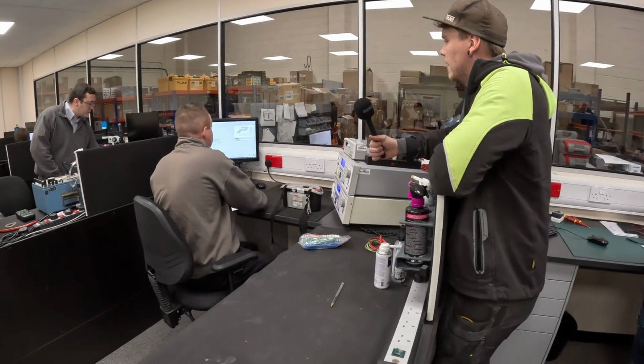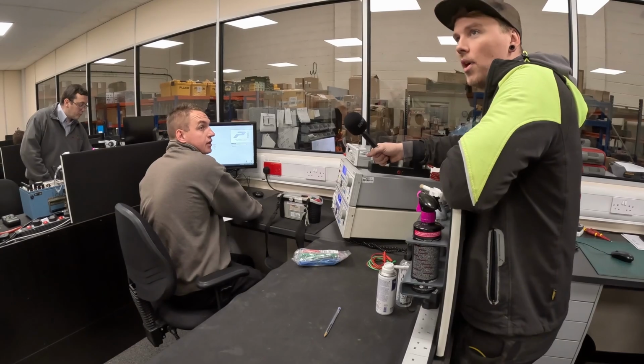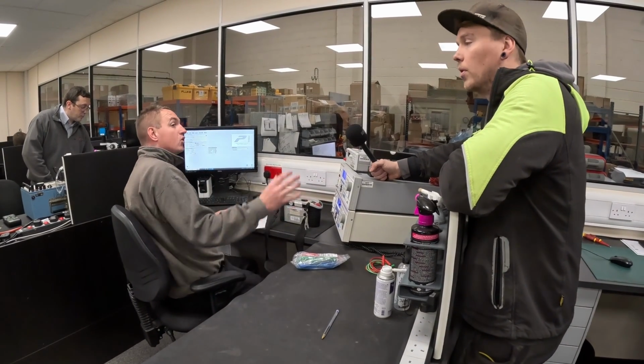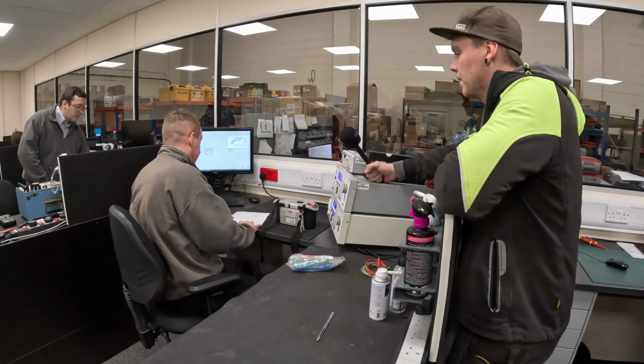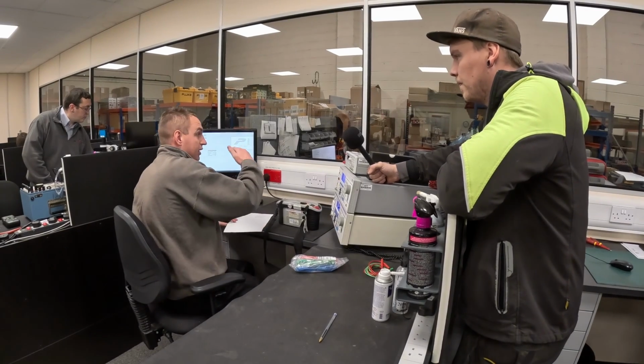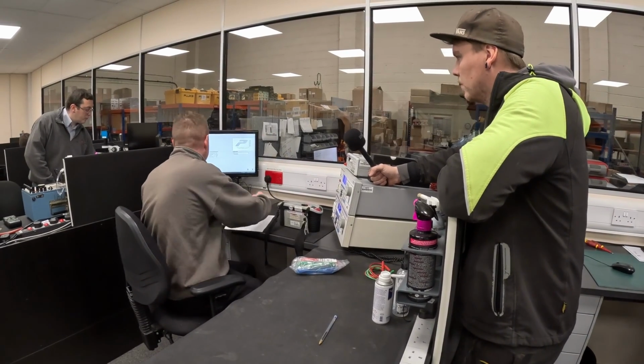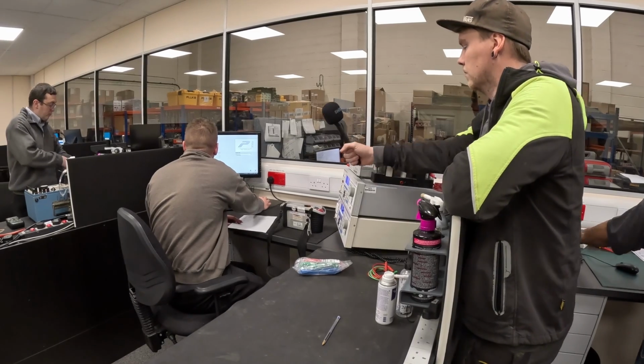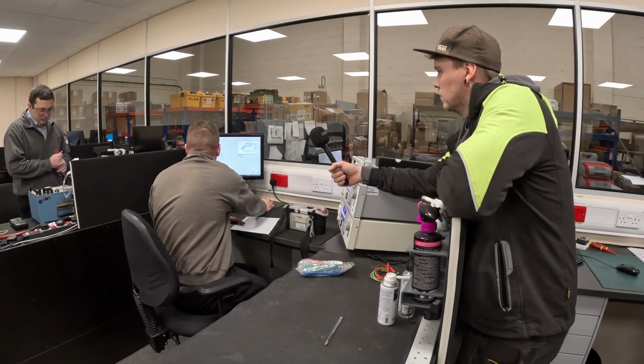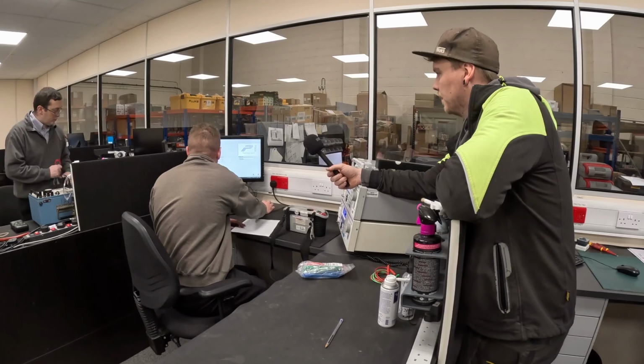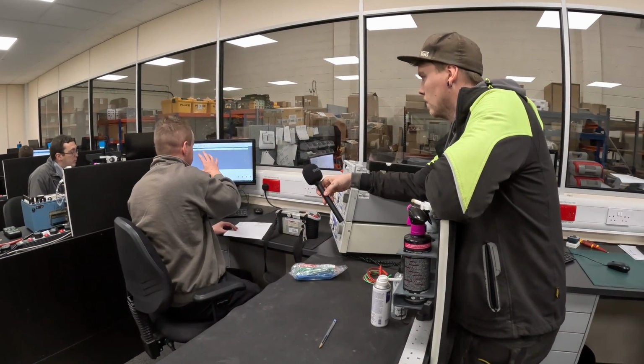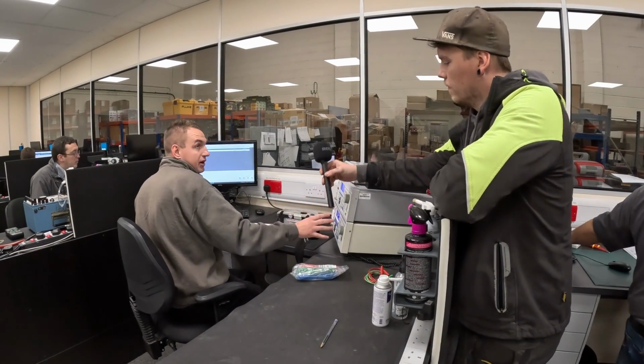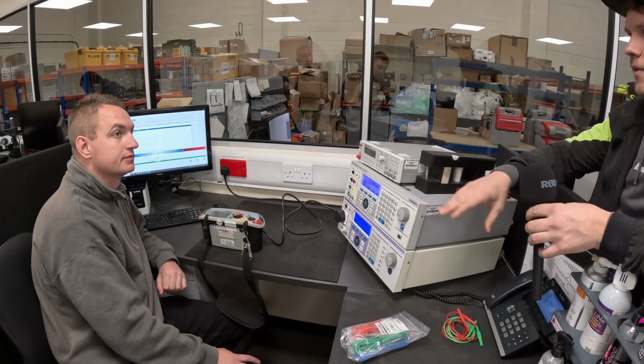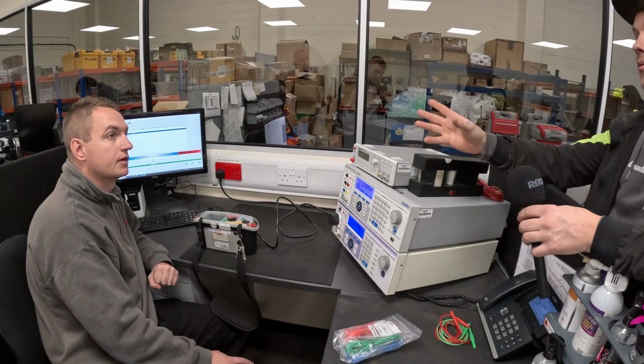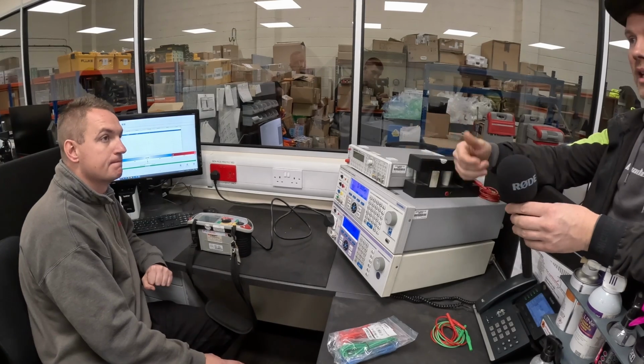Does it come up with old past MOTs or old calibrations, does it all pop up of what it's failed before? You can look at the history of the unit, yes - you can go back onto the history and have a look to see previous years. It'll bring up all your details, serial number, address, and who's calibrating it - myself - and then you just select the actual meter itself for the actual calibrator. This is all set to the pass and fail limits of what it should be calibrated to, so you plug it in, it does itself on the screen, and then you just say yes or no.